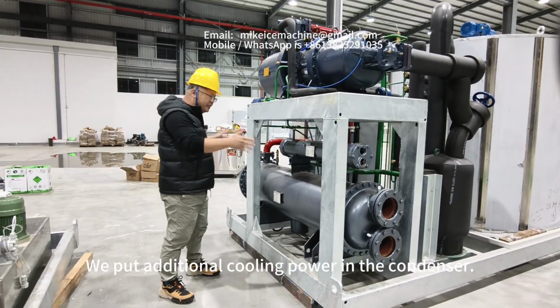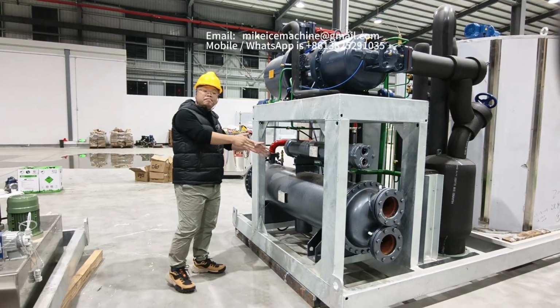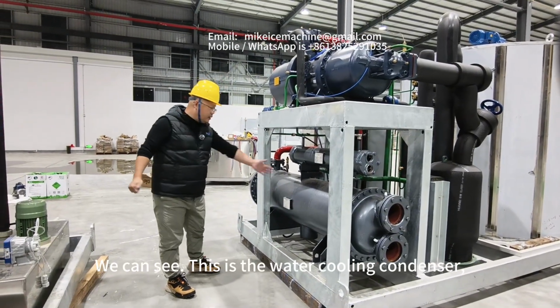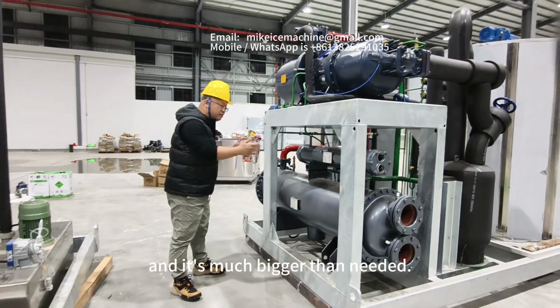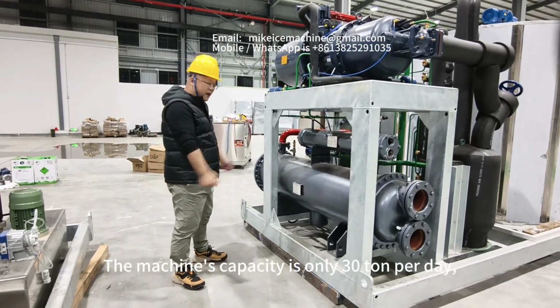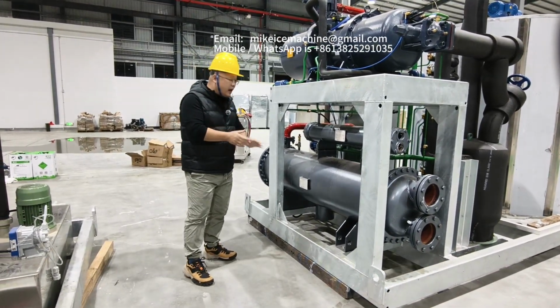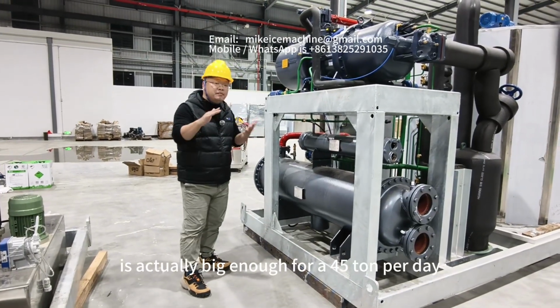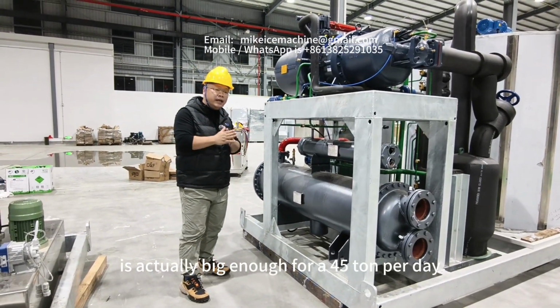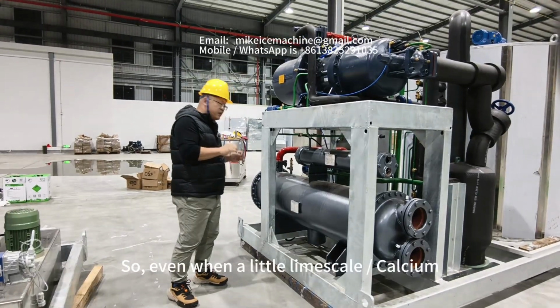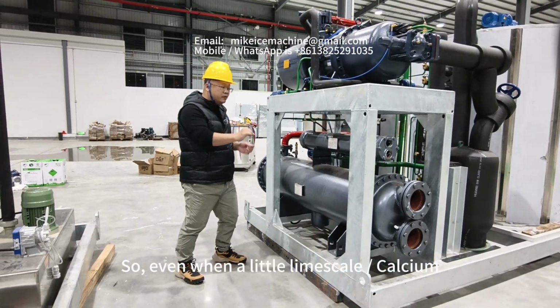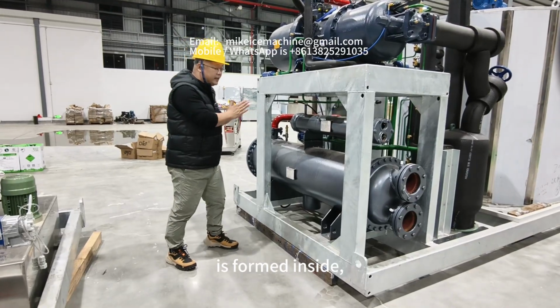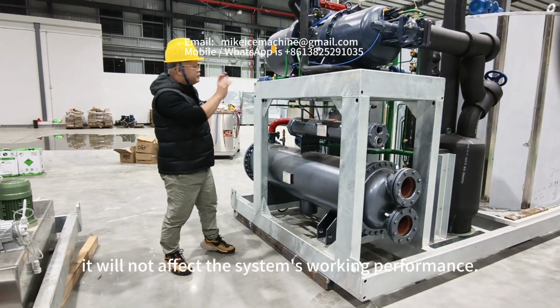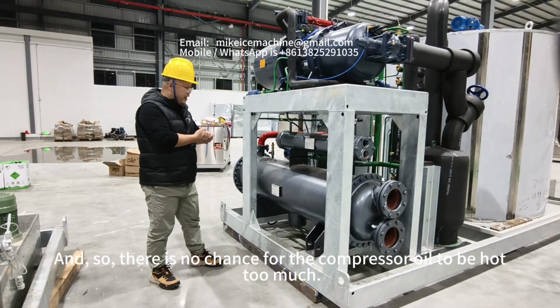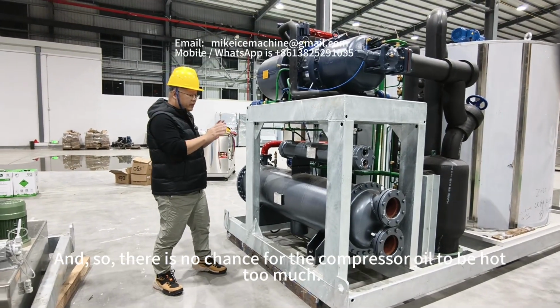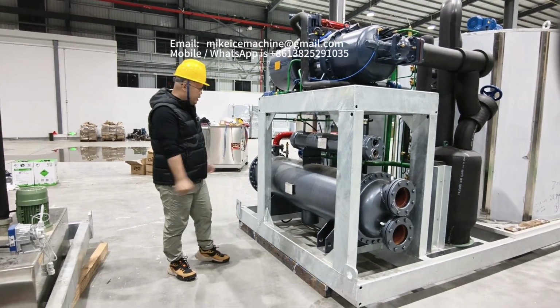We put additional cooling power in the condenser. This is the water cooling condenser, much bigger than needed. The machine's capacity is only 30 tons per day, but this condenser is actually big enough for a 45 ton per day machine. So even when a little lime scale of calcium forms inside, it won't affect the system's performance, and there's no chance for the compressor oil to get hot.